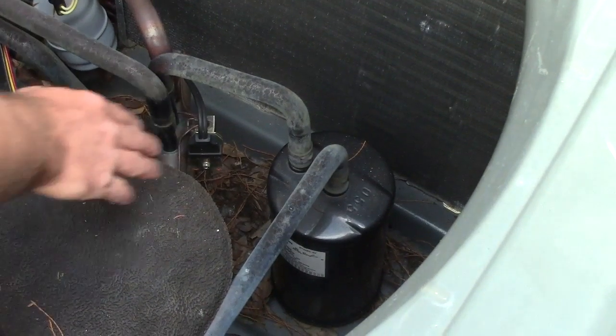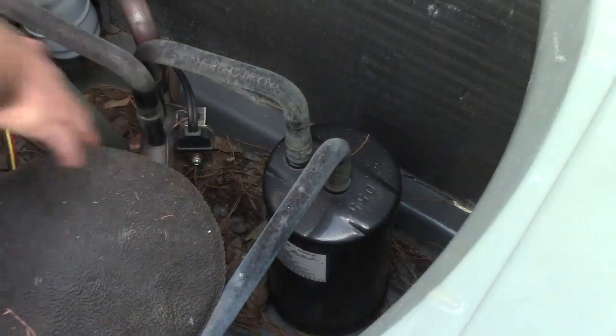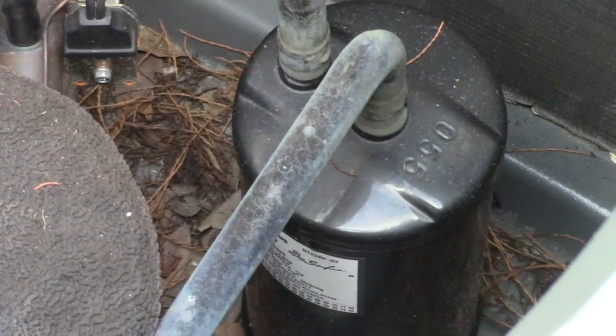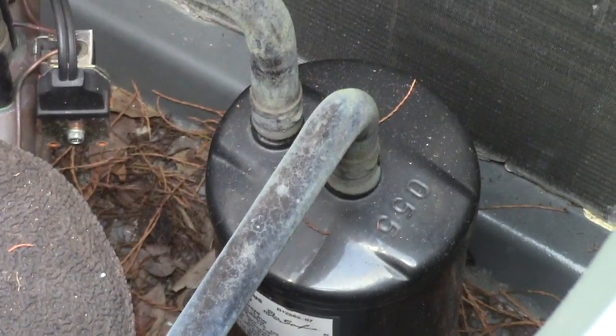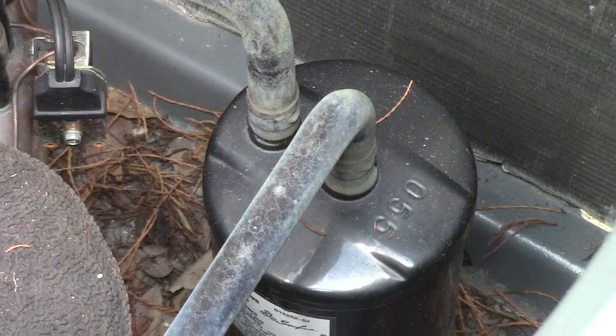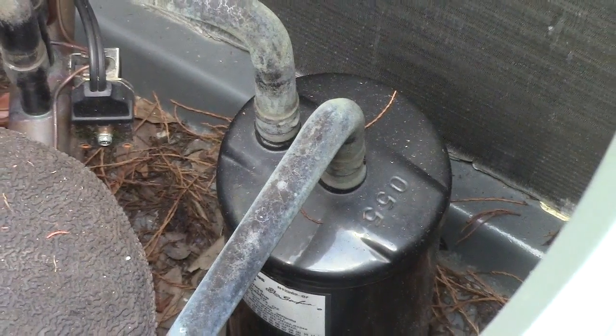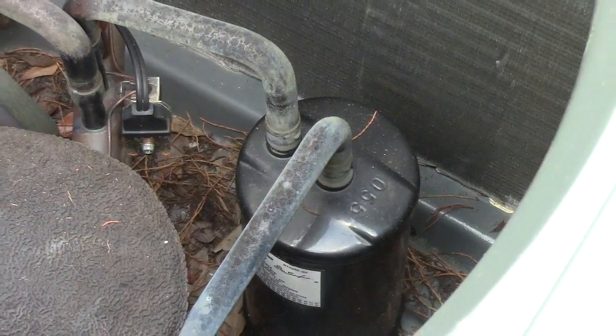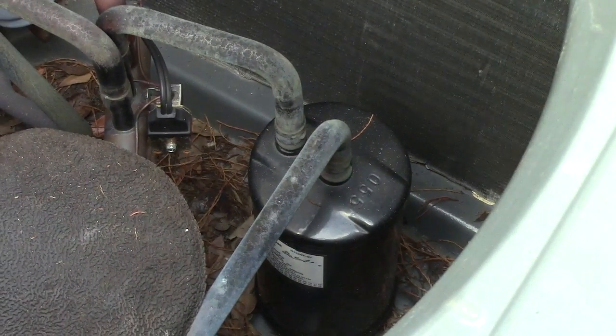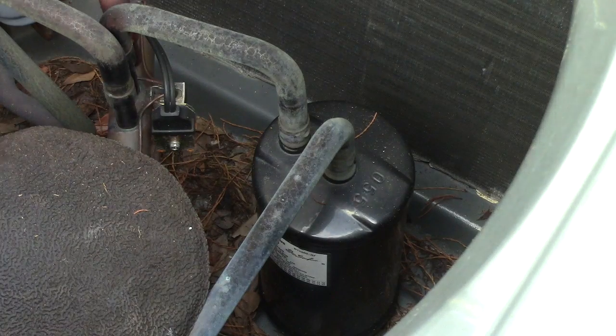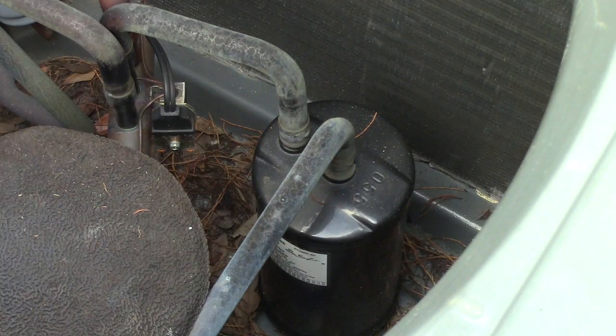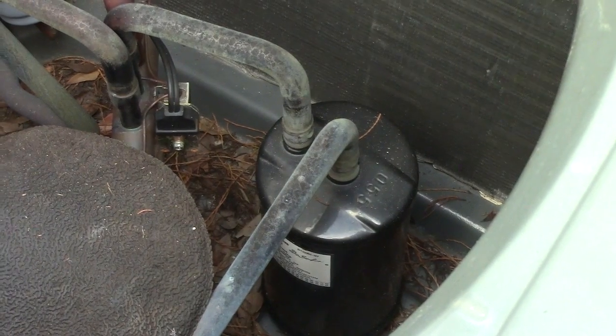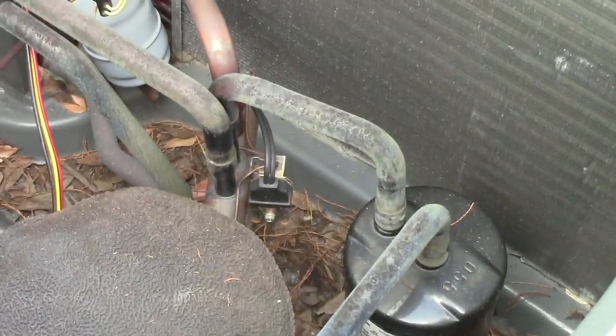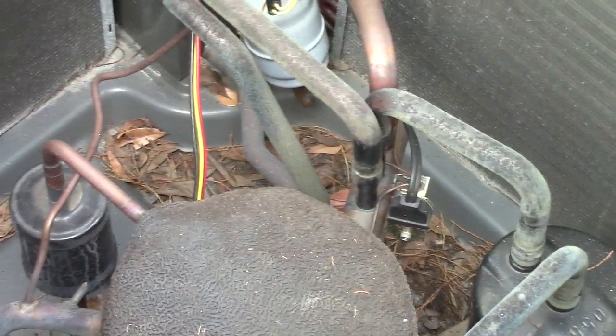Right next to the compressor over here, this is a device called the accumulator. The accumulator is a component built of steel. It is always cold, it is always wet. It will eventually rust and rot and will eventually leak. It is guaranteed. We recommend replacing these every 10 to 12 years upon condition. These are a lot of the components that we're focused on during a checkup to make sure that you are not going to be stuck without heat or air when the time is in need.